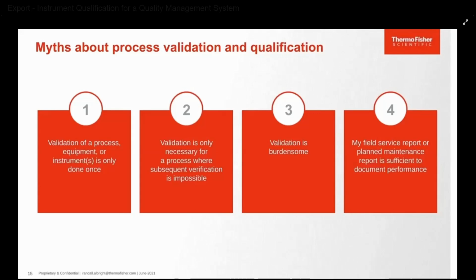The intent of a service report is to document the scope of the service event being performed. A maintenance protocol's intention is to document the manufacturer's recommended maintenance activities to be performed. Only a qualification is the industry-accepted mechanism to document performance as called out in the guidance documentation from the International Medical Device Regulators Forum and FDA Medical Device Quality Systems Requirements we spoke about earlier in the webinar.